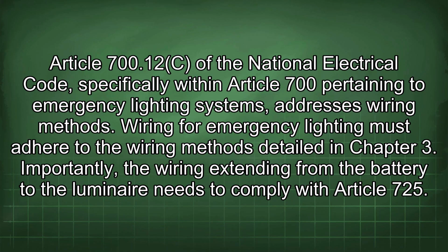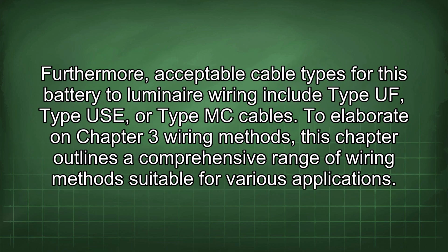Article 700.12c of the National Electrical Code, specifically within Article 700 pertaining to emergency lighting systems, addresses wiring method. Wiring for emergency lighting must adhere to the wiring methods detailed in Chapter 3. Importantly, the wiring extending from the battery to the luminaire needs to comply with Article 725. Furthermore, acceptable cable types for this battery to luminaire wiring include Type UF, Type USE, or Type MC cables.